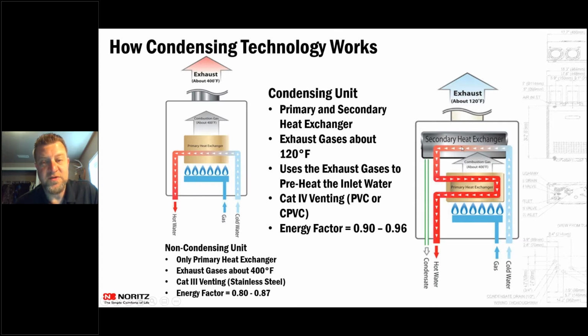So we're taking the temperature and the heat from those flue gases and injecting those into that water that's coming in through the unit. So it's actually cooling those stack temperatures down. So the exhaust coming out of the top of that unit is about 120 degrees. It can be cooler than that, depending on how much that secondary heat exchanger is actually pulling through.